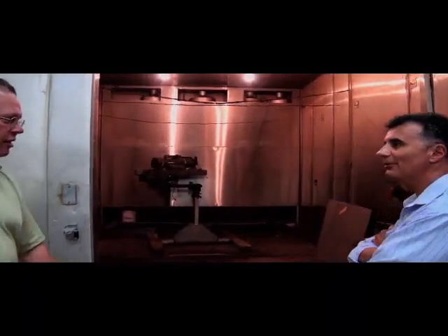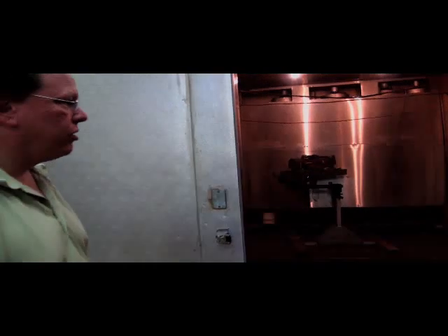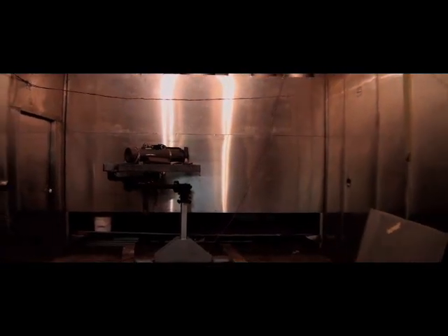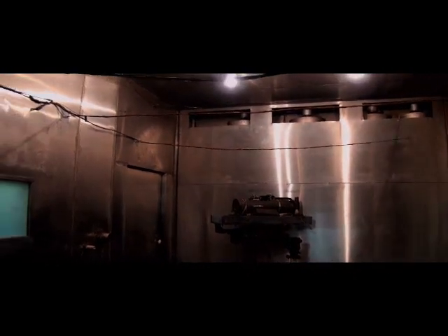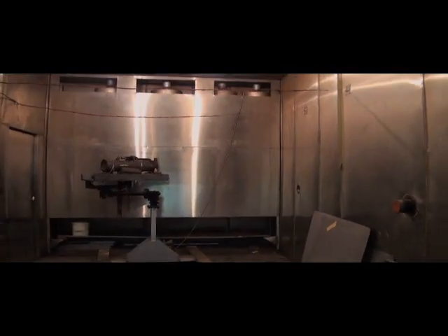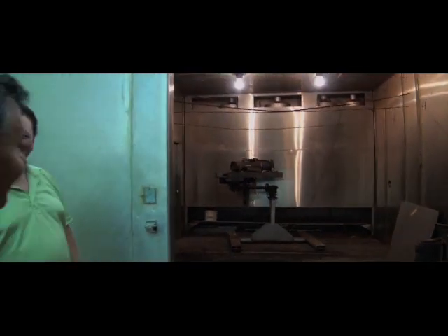What's the capability of this chamber? This chamber will handle minus 65 degrees F up to about 200 degrees F on the high side. It'll handle that temperature with a 90,000 BTU an hour heat load inside the room. This chamber is about 10 feet wide, 10 feet tall, and 14 feet deep.